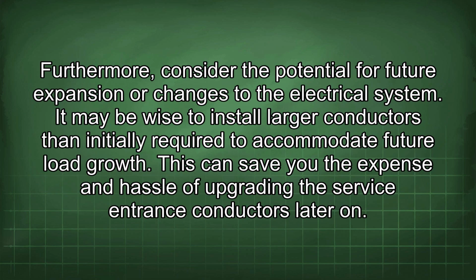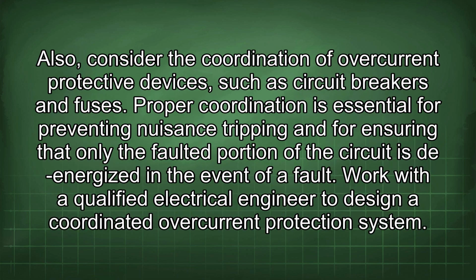Furthermore, consider the potential for future expansion or changes to the electrical system. It may be wise to install larger conductors than initially required to accommodate future load growth. This can save you the expense and hassle of upgrading the service entrance conductors later on. Also, consider the coordination of overcurrent protective devices such as circuit breakers and fuses. Proper coordination is essential for preventing nuisance tripping and for ensuring that only the faulted portion of the circuit is de-energized in the event of a fault. Work with a qualified electrical engineer to design a coordinated overcurrent protection system.